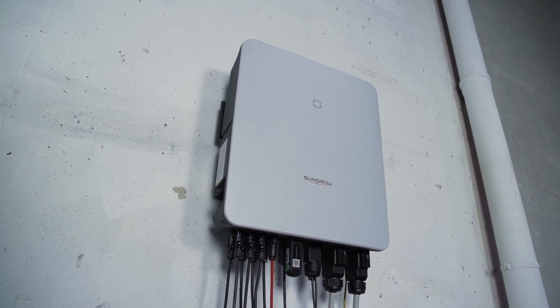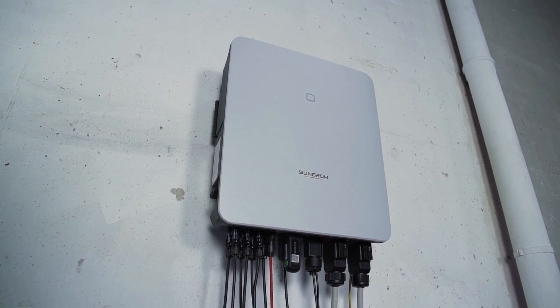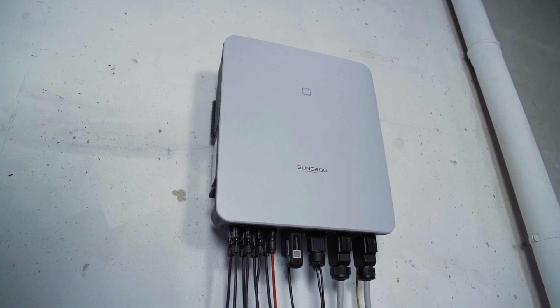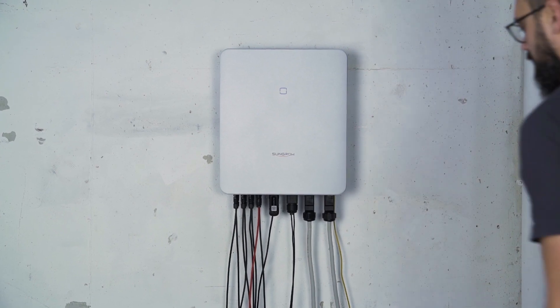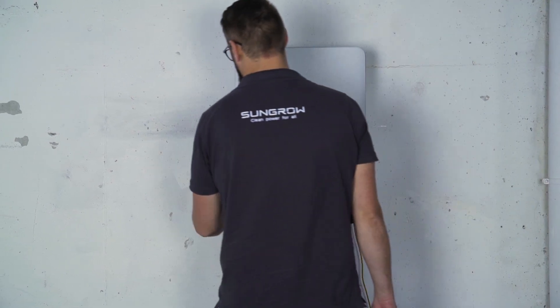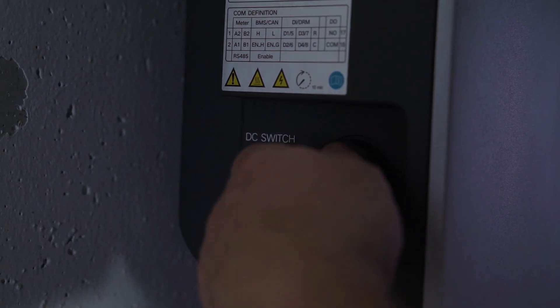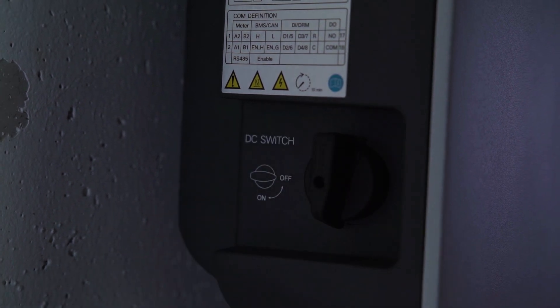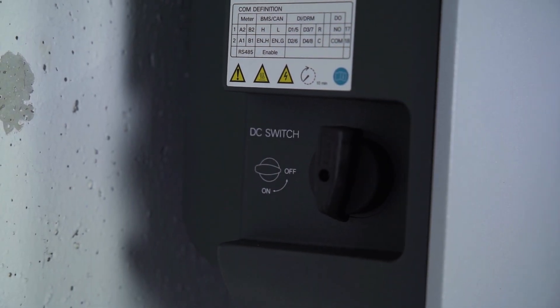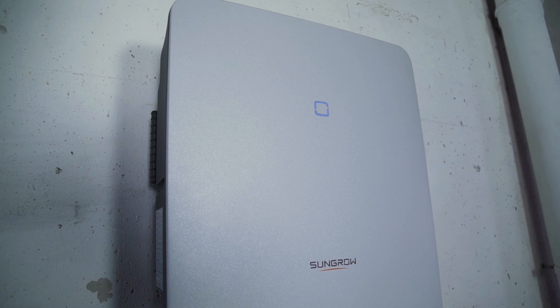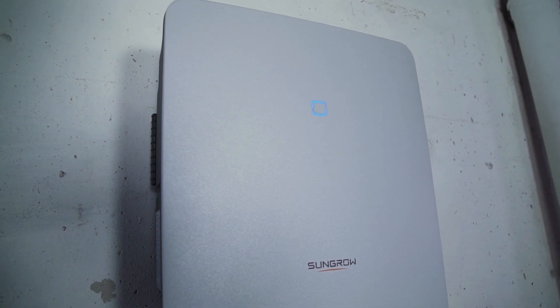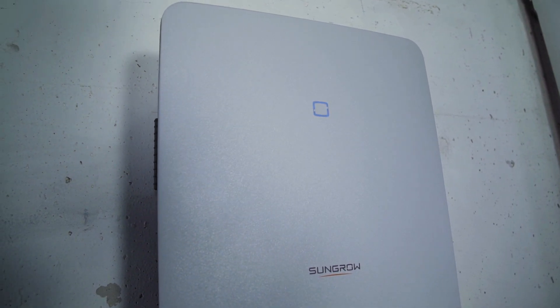Now it's time for commissioning. First you have to switch on the AC circuit breaker. Next, set the DC switch on the left side of the inverter to the on position to connect the inverter to the PV generator. A look at the LED light tells you if everything works properly. If the light shines continuously blue, the inverter is ready for use.